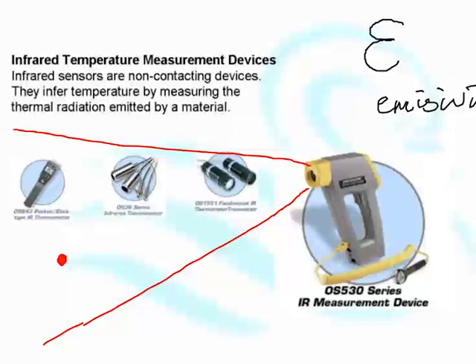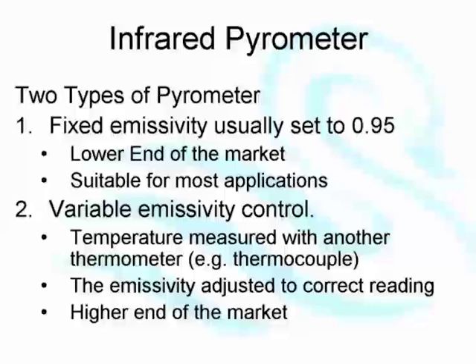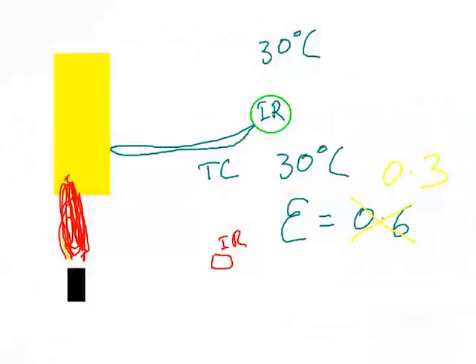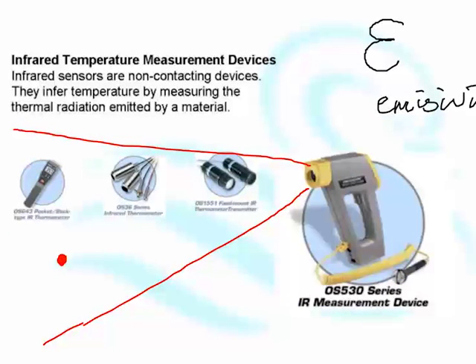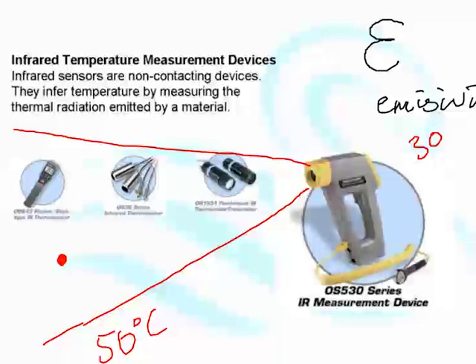If you don't have a thermocouple, then what you would do, I guess, is take the temperature of the device that you want to measure using some other type of temperature measuring thing, maybe even a bulb thermometer, and from that calculate how far out your infrared sensor is and adjust the emissivity in your infrared sensor until it reads correctly. So you point the thing at the object you want to measure. If the thermometer is reading, say, 50 degrees C, and your infrared sensor is reading 30 degrees C, then you adjust your emissivity until both of them agree. And then your infrared gun is calibrated for measuring that particular object, and only that particular object.